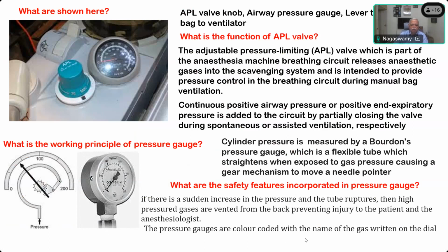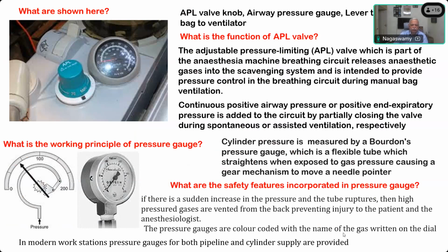Pressure gauge is color coded with the name of the gas written on the dial. And in modern workstations, pressure gauges for both pipeline and cylinder supply are provided. Whereas in the earlier machines, only the cylinder mounted pressure can be read from this. The pipeline pressure or central supply pressure will not be there. But in your modern workstations, you will find both the pipeline supply pressure as well as the cylinder supply pressure. All these things are added advantages or safety features.